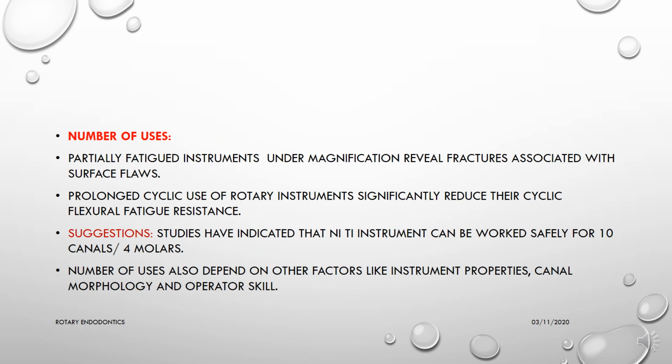How many times can rotary files be used? Partially fatigued instruments under magnification have revealed fractures associated with surface flaws. Prolonged cyclic use of rotary instruments significantly reduces their cyclic flexural fatigue resistance. Studies have indicated that NiTi instruments can be used safely for 10 canals of 4 molars, but the number of uses also depends on other factors like instrument properties, canal morphology, and operator skill. So most manufacturers suggest the rotary files be used only once to prevent instrument fracture within the canals.